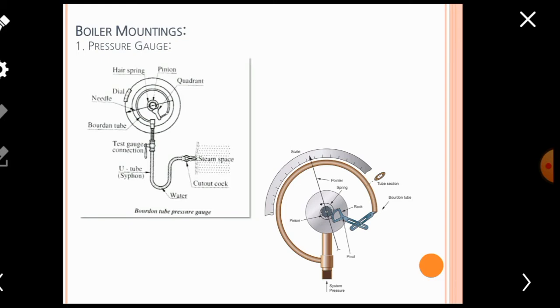The Bourdon tube mounted centrally in the body has an elastic nature — if you apply pressure or force on it, it will change shape according to the applied pressure magnitude, but after removing that force it will regain its original shape and size due to its elastic property. The cross-section of the Bourdon tube is elliptical in shape. Whenever the pressure of steam acts on this elliptical internal cross-section, it will try to become circular from elliptical.